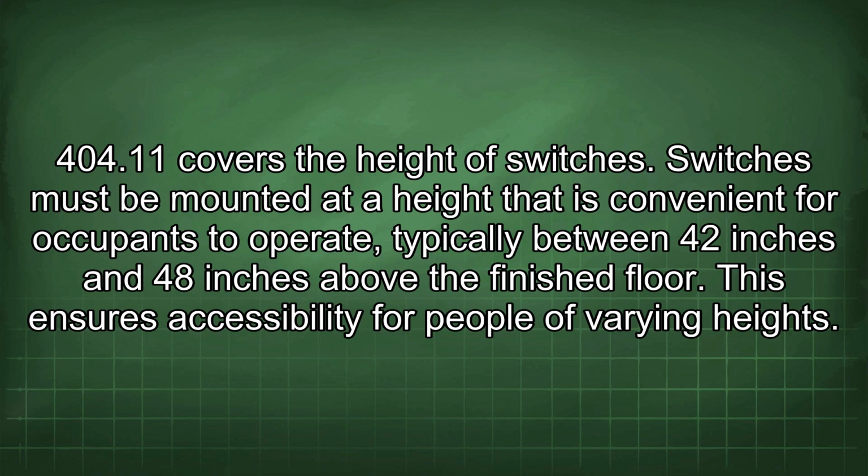404.11 covers the height of switches. Switches must be mounted at a height that is convenient for occupants to operate, typically between 42 inches and 48 inches above the finished floor. This ensures accessibility for people of varying heights.